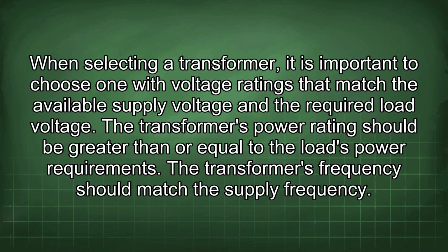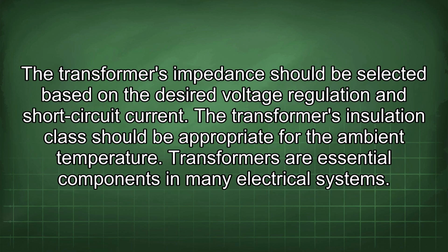When selecting a transformer, it is important to choose one with voltage ratings that match the available supply voltage and the required load voltage. A transformer's power rating should be greater than or equal to the load's power requirements. The transformer's frequency should match the supply frequency. The transformer's impedance should be selected based on the desired voltage regulation and short-circuit current. The transformer's insulation class should be appropriate for the ambient temperature.